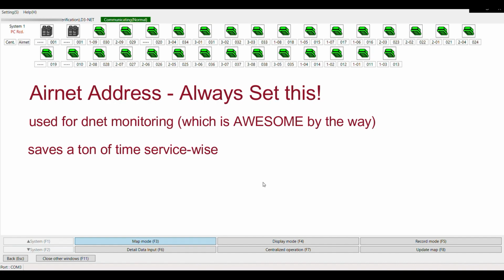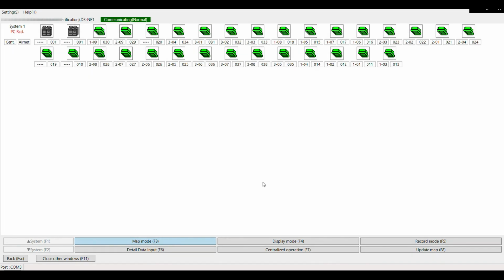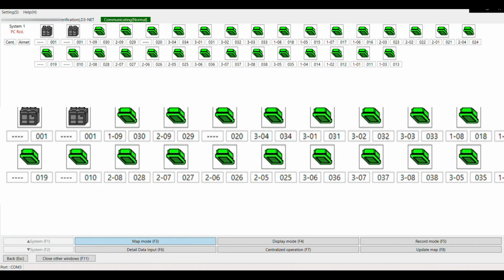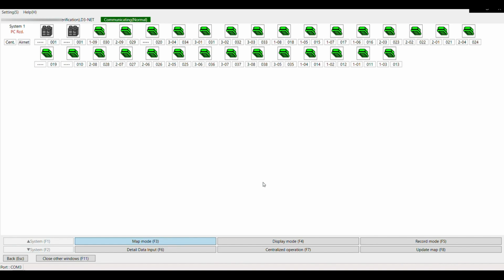There is one other very important reason for these AirNet addresses to be set as well. Take a look at the icons once more. You'll see that not all indoor icons display a group address. This happens when two or more indoor units are part of the same group. Only one indoor unit within the group will display the group address. The others will not. By programming AirNet addresses into each unit, we can see very specifically which unit is which. This is going to be very important shortly when we're looking at raw data points to check the branch box ports for cross-wiring. I'll explain this more in detail shortly.